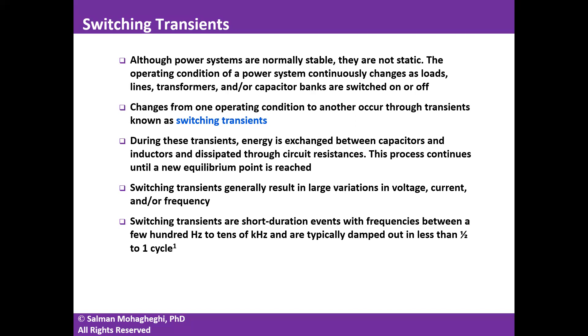The change from one operating condition to another does not happen smoothly. Typically, this happens through a transient — a high-frequency oscillation in voltage and current and frequency — while you go from one stable operating condition to another stable equilibrium. Fortunately, we have enough resistance to damp out these oscillations fairly quickly, usually within one cycle of power frequency, one cycle of 60 Hz.